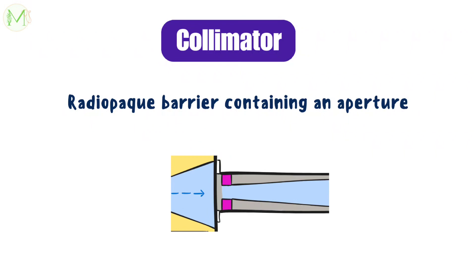Collimators decrease the scattered radiation and reduce the size of the X-ray beam. Therefore, the volume of the irradiated tissue in the patient reduces. It also reduces the patient exposure due to its small X-ray field, and it provides better contrast and increases film quality.